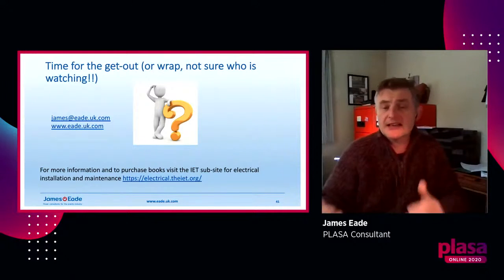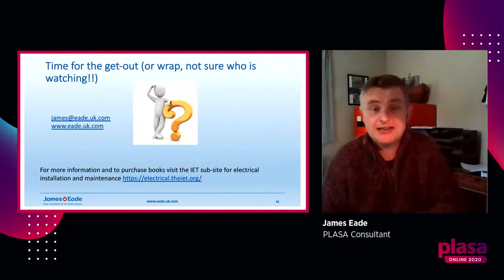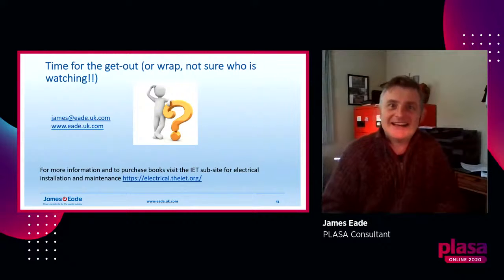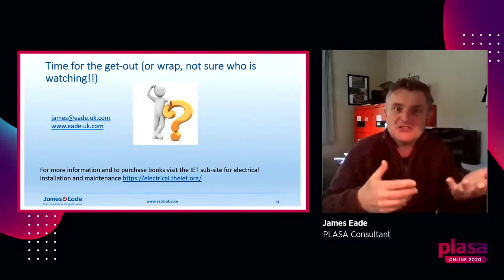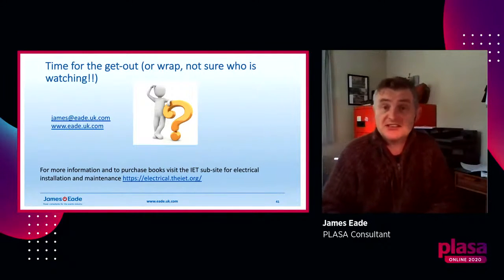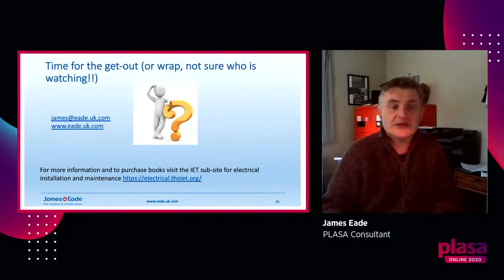And in terms of recording, because it's your own kit, what I do is just do your documented PAT policy, for want of an electrical equipment safety testing policy, for want of a better description, and just outline what you do, what checks you do every time you use the kit, how it's stored, the environments you work in and everything. Do that risk assessment, decide what you want to do and stick with it. And again, that's a perfectly reasonable way.